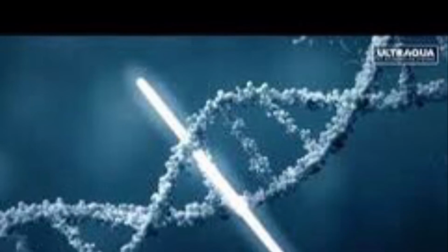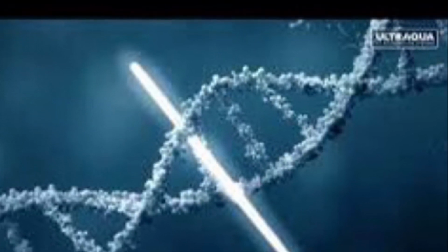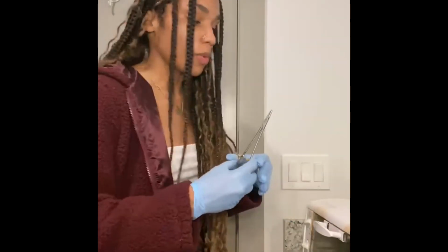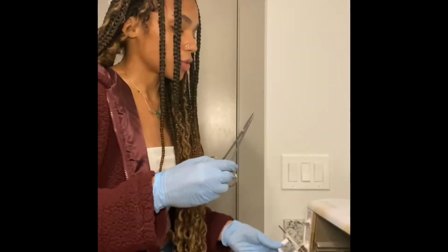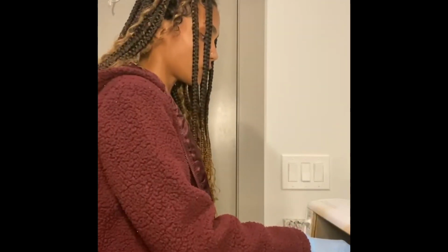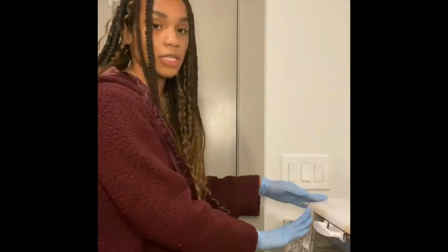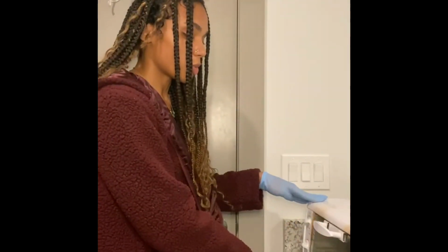Instruments would be placed onto the metal tray, the door would be closed, and the desired cycle of sterilization would begin. In order to better understand the simplicity of our design, I will be doing a quick demonstration with a pair of needle drivers. If you are a midwife intending to sterilize these needle drivers using our UV light sterilization box, you would place all instruments on the metal removable tray, close the door, and choose the intended cycle that you would like all instruments to run on.